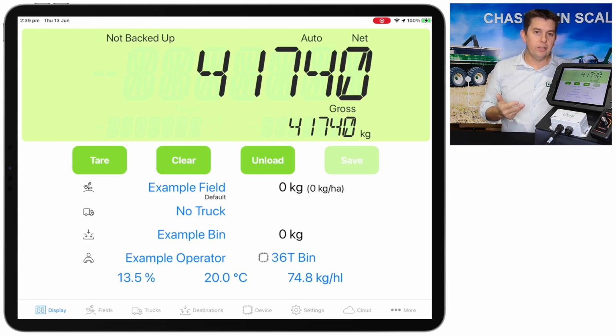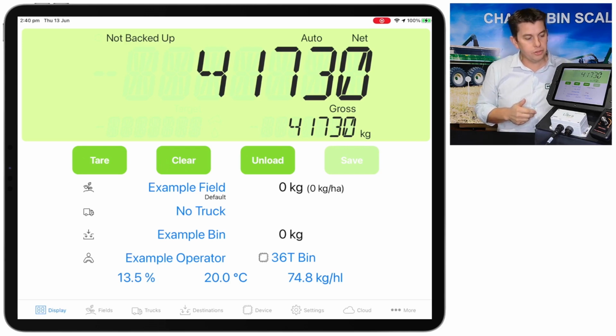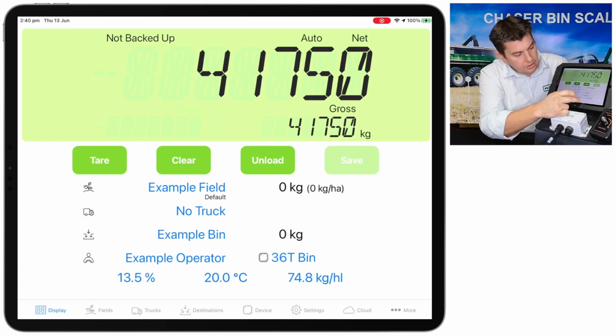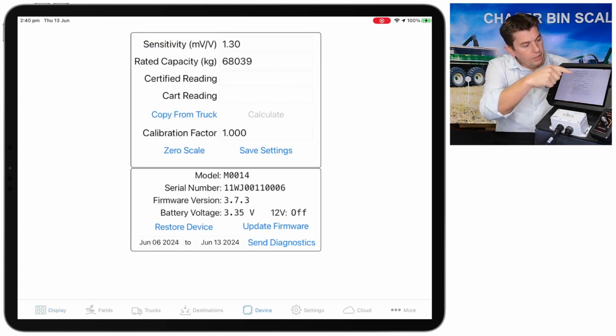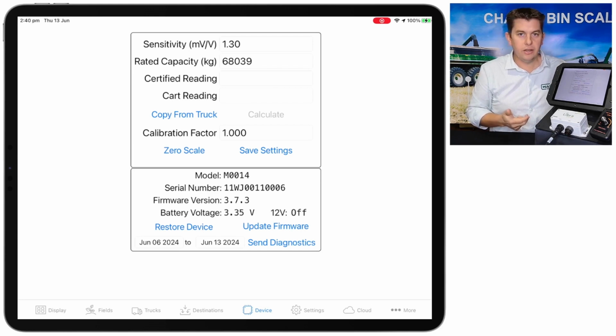We can now refine the calibration, and we can do that with checking a truckload over a weighbridge, and there's a little inbuilt calculator in there to help us do that. So we go back to the device tab, and then you'll see certified reading and cart reading. So that's the little inbuilt calculator to help us refine the calibration to get the bin as accurate as possible. So certified reading is a known weight, so the truckload over the weighbridge, and the cart reading is what the bin said we put into the truck.